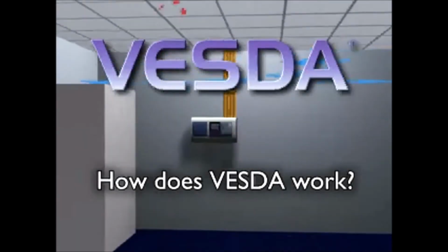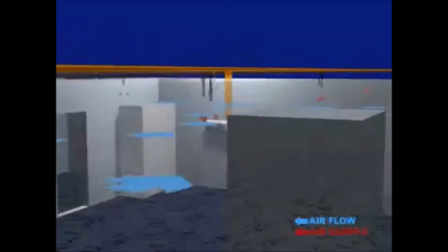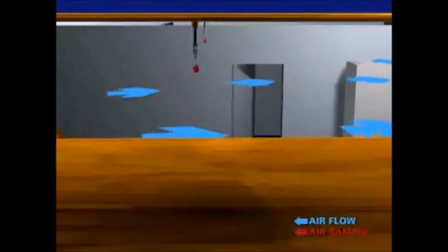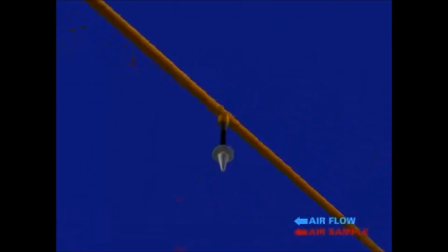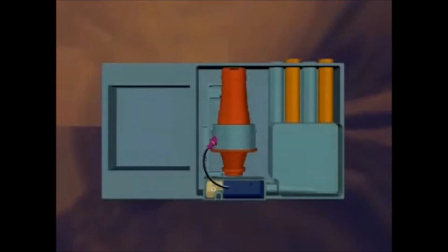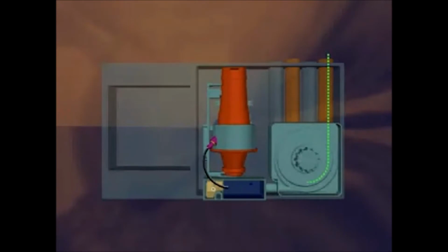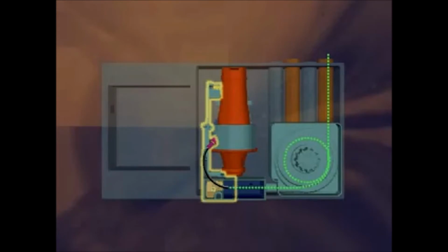So how does the VESDA detection system operate? Here's an overview. VESDA is an active system, continuously drawing air through multiple sampling holes along a network of pipes. These pipes transport the air to a central, highly sensitive detector. Prior to entering the chamber, the air sample passes by a flow sensor through the aspirator and a dual-stage filter. During the first stage of filtration, dust and dirt are removed from the air. A portion of the sampled air goes through the second ultrafine filtration stage and introduces clean air that forms a protective barrier, keeping the optical components within the chamber free from contamination.